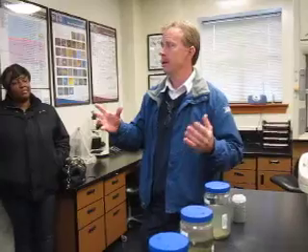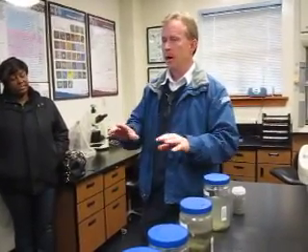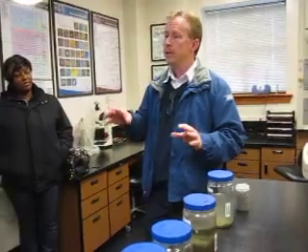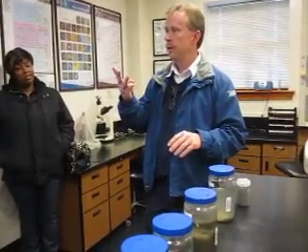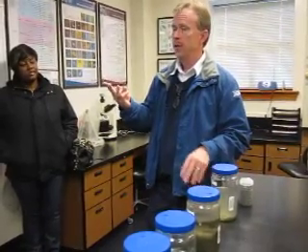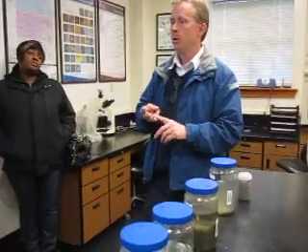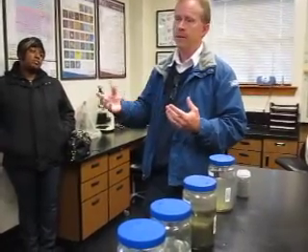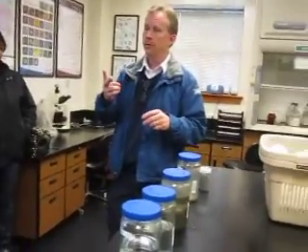We do have a secondary clarifier out of service. It's kind of related to the rain and excess flow coming into the plant. No pipelines are down though. But we do have a secondary clarifier down. Normally we have 3 clarifiers in operation. They all have a rated treatment capacity, and when you bring one down for maintenance, that takes away from your total treatment capacity. So you're pushing more flow through 2 clarifiers.